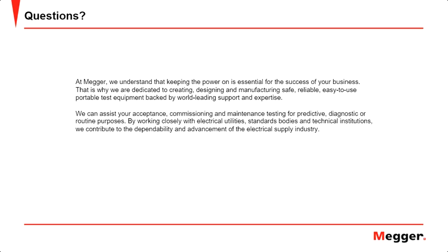Thanks, Yash. Going back over to Chase, what is the relation between water tree and TD values? The water tree and TD values depend on how big that water tree actually is. If it's been forming for a long time, you may see higher tan delta values within that cable.